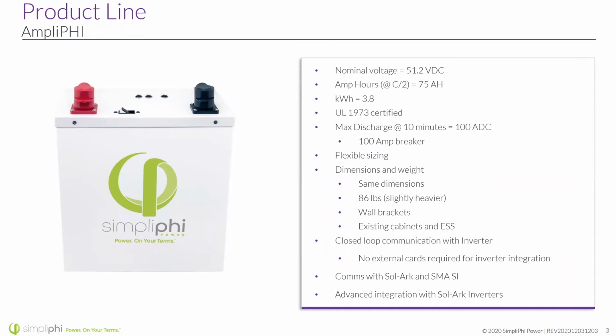You will notice one big difference here in the upfront specs: max discharge on the Phi battery is 480 amps, while for the AmpliPhi battery it's 100 amps. That comes with the 100 amp breaker as well, so it has a bit higher surge capacity at that 10-minute mark. Flexible sizing—we'll talk more about that later—but for those aware of our sizing requirements, this one has more flexibility when it comes to a smaller battery and larger inverter.